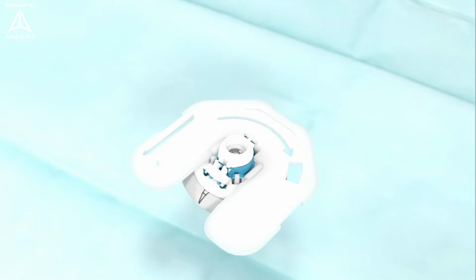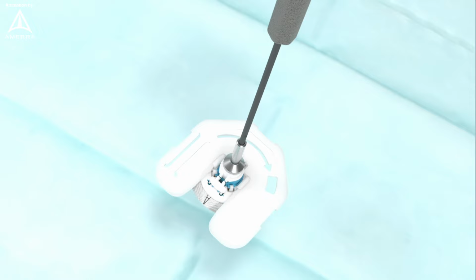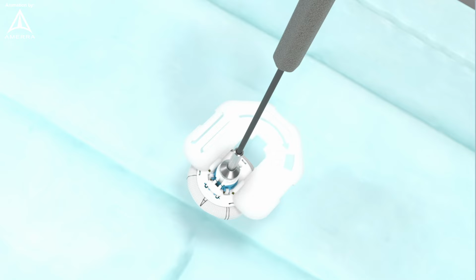Next, attach the model 1140M handle. To attach, align the handle with the adapter on the valve holder and turn clockwise until resistance is felt. To remove the retainer, hold the base of the handle and pull the retainer away by grasping the ridge on the narrow edge of the retainer. The valve is now ready to be passed to the surgeon.